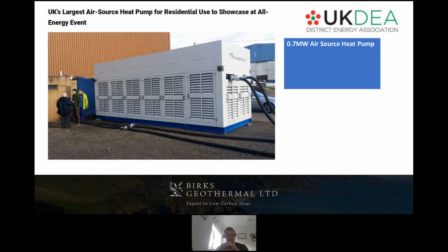So whilst the size of the unit itself is very similar to a similarly sized water source heat pump, the area or the space around an air source heat pump, which effectively could become sterilized, is actually quite a lot larger than the unit itself, and I think is something that should feature in the capex evaluation of this and other technologies. I think there's a general presumption that an air source heat pump system is a lower capex option than a water source, because you're simply sucking in the air which is ever present, rather than having to couple to an external water harvesting network.